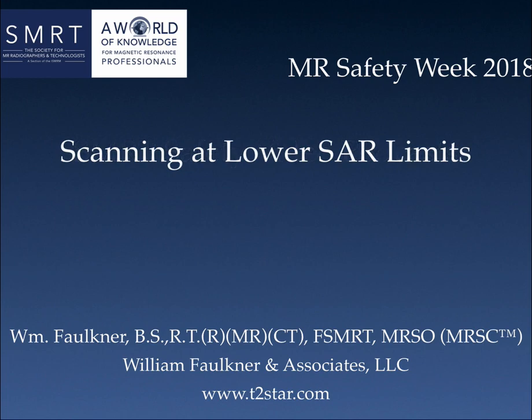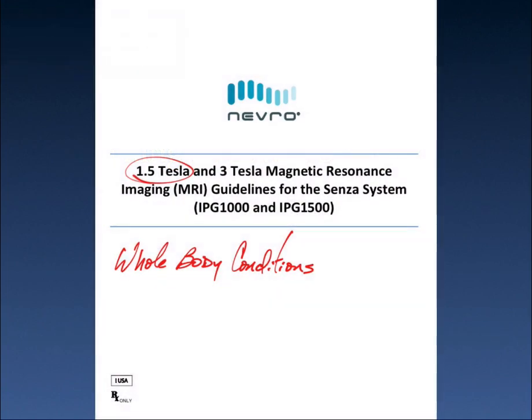In this first video, we're going to take a look at performing an MRI exam on a patient using lower SAR values — in particular, a lumbar spine exam with an SAR value of 0.4 watts per kilogram. Conditions of use like this are usually required when you image patients with particular implants or devices. In this example, we're going to be following the conditions of use of a NEVRO spinal cord stimulation system, specifically the SENZA system.